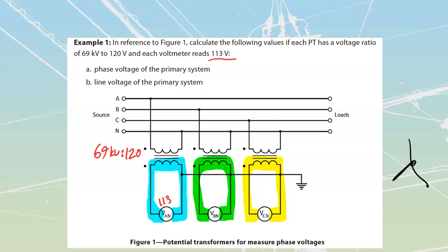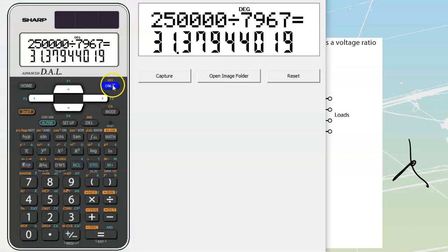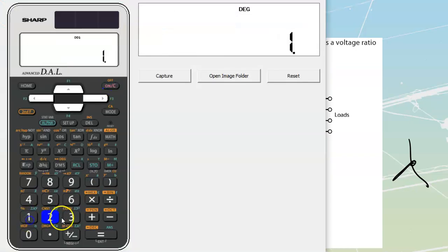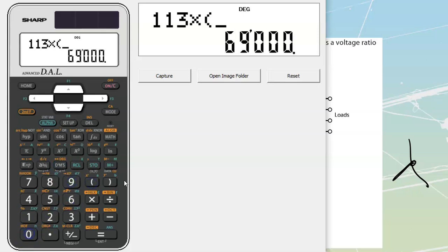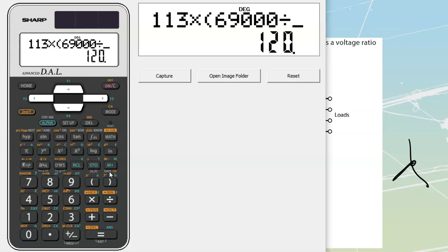We're just going to take our secondary actual side, 113, and multiply it by my ratio, 69,000 over top of 120. And that's going to bump us up to our high side. Let's do so. We are going to take 113 multiplied by 69,000 divided by 120, which is going to get us to a value of 64,975 that we will have.